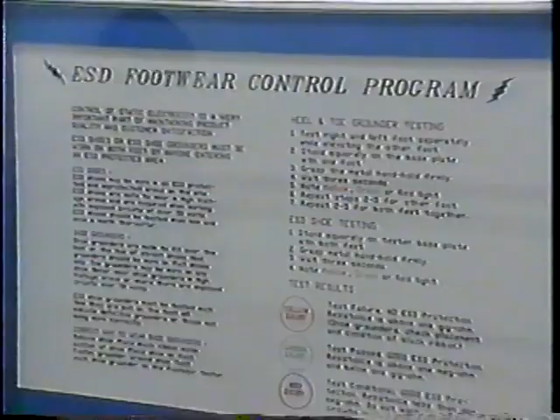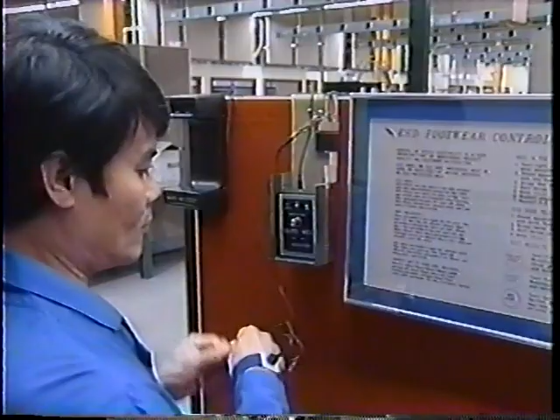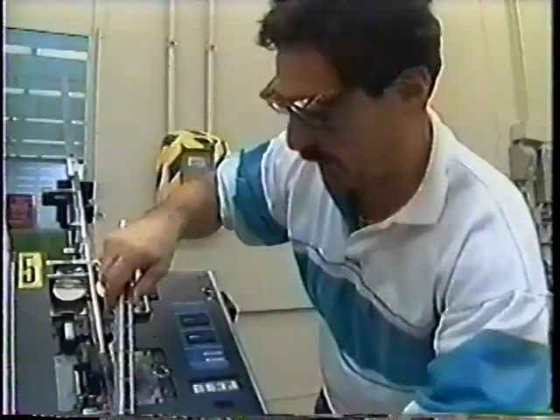In an electrostatic discharge protective area, all static electricity is controlled and doesn't present a threat to ESD sensitive product. Everybody and everything is at ground potential, meaning no significant static electricity on its surface. To keep everything at ground potential, entrance to the area is controlled. Protective garments are worn when required because the components being handled are very sensitive to ESD. All workstations, furniture, and equipment are ESD protective. Static-generating personal items made of plastic, like picture frames, radios, and holiday decorations, are eliminated or controlled. Because everything is at ground potential, ESD sensitive product may be moved around without worrying about damage from electrostatic discharge. Requirements for an ESD protective environment may vary from company to company.